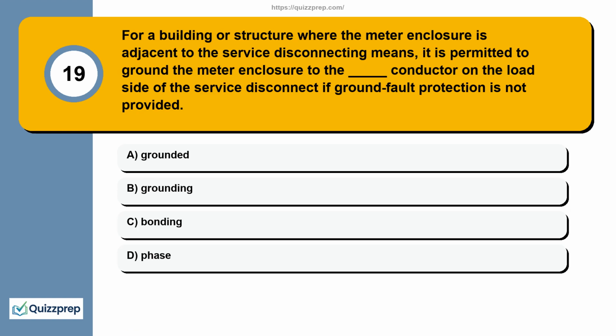Question 19. For a building or structure where the meter enclosure is adjacent to the service disconnecting means, it is permitted to ground the meter enclosure to the conductor on the load side of the service disconnect if ground fault protection is not provided. Grounded, grounding, bonding, phase.